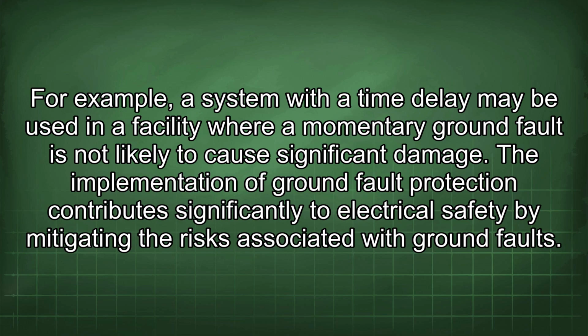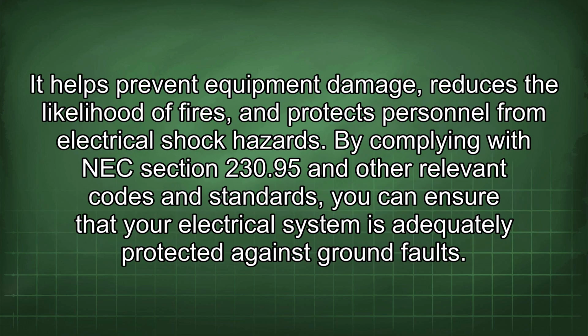The implementation of ground fault protection contributes significantly to electrical safety by mitigating the risks associated with ground faults. It helps prevent equipment damage, reduces the likelihood of fires, and protects personnel from electrical shock hazards. By complying with NEC Section 230.95 and other relevant codes and standards, you can ensure that your electrical system is adequately protected against ground faults.